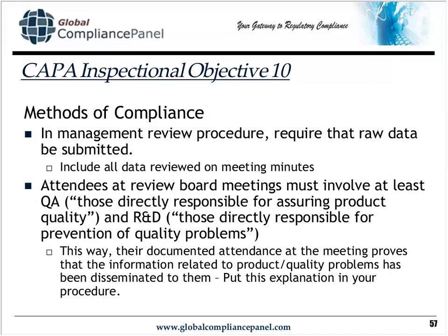In your management review procedure, you want to require that raw data be submitted. This is just a recommendation that I do meet with a bit of resistance, and I'm okay with it being summary data instead of raw data. The reason I tend to recommend raw data is it's an absolute compliance. You are in 100% compliance this way. But as I said earlier, in my very recent experience at least, the inspectors give us a little leeway when it comes to evaluating to what extent CAPAs have been submitted for management review. So not so much raw data, but at least summary data, something that is significant and explains the corrective action taken.